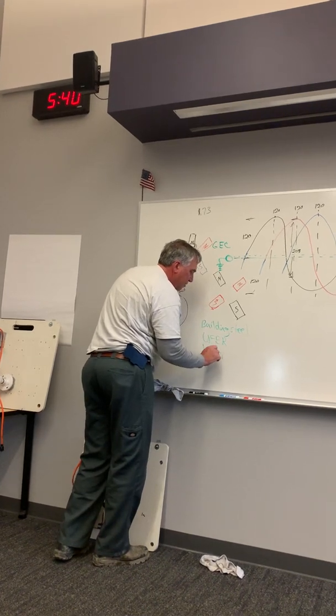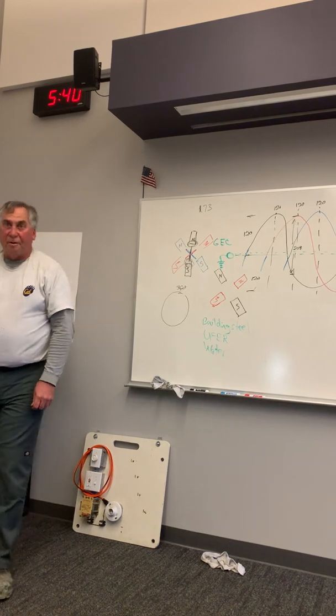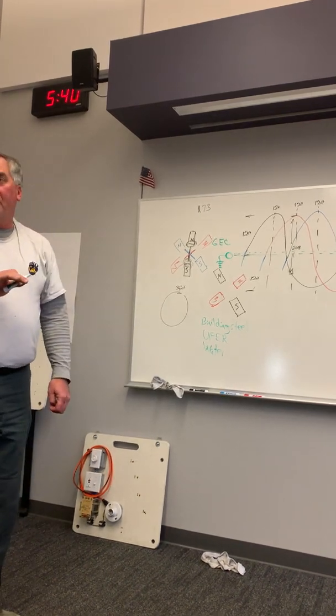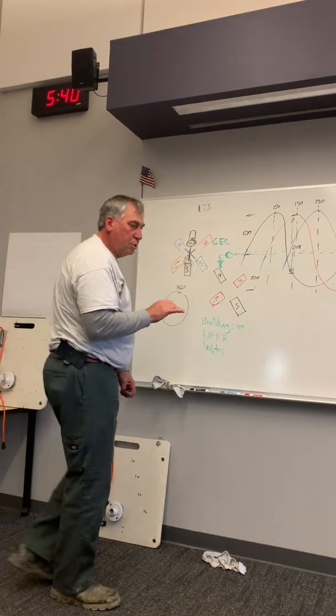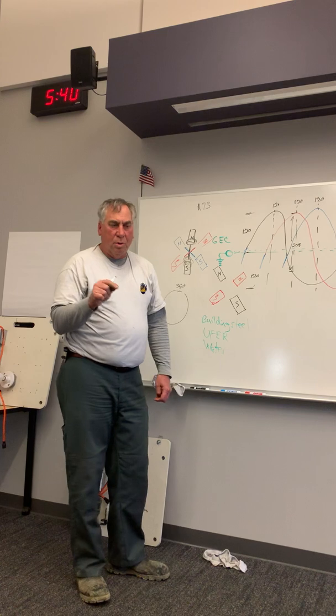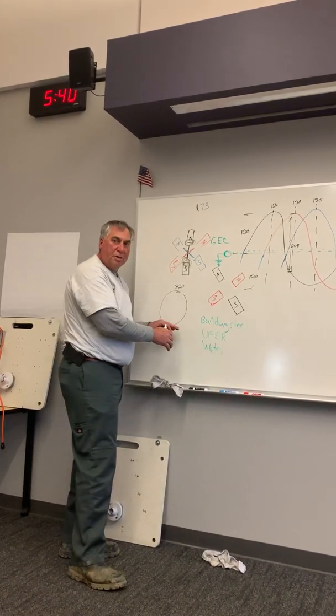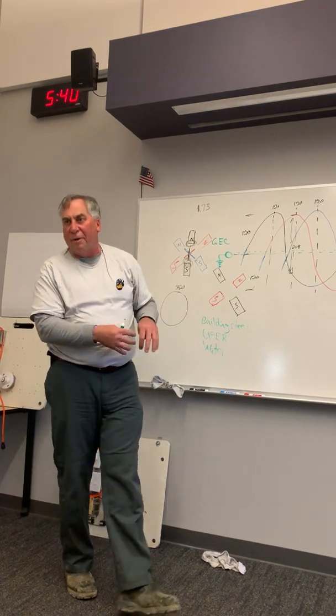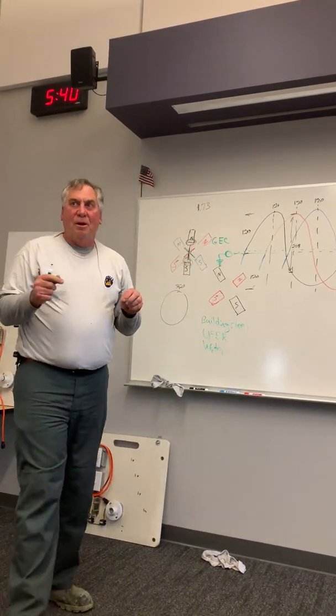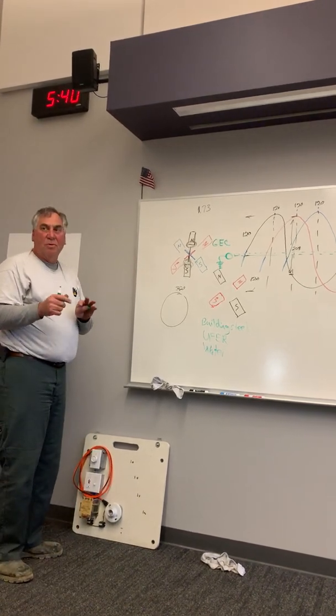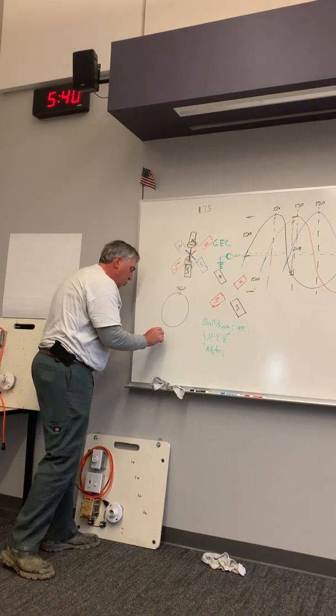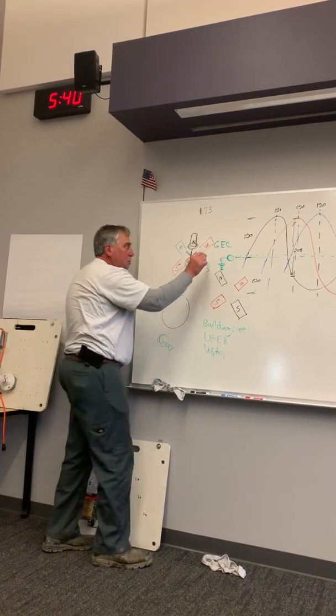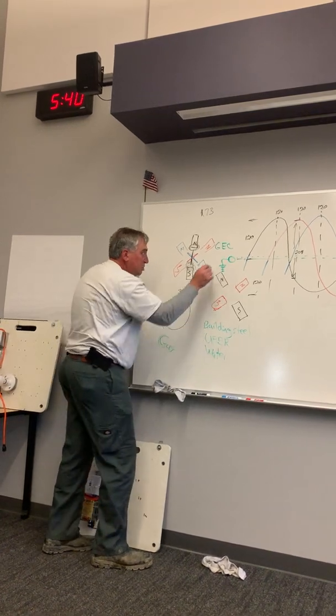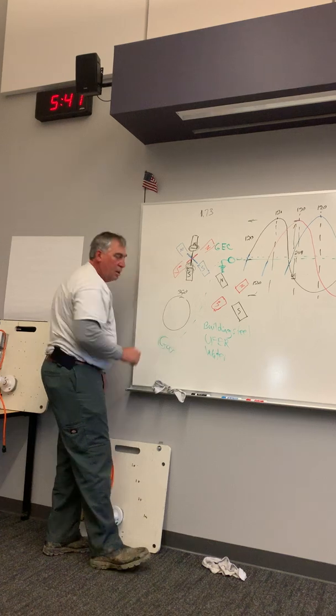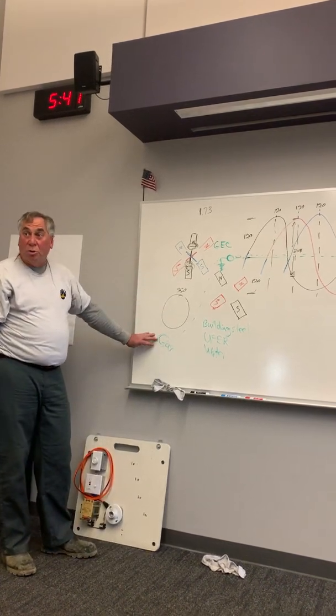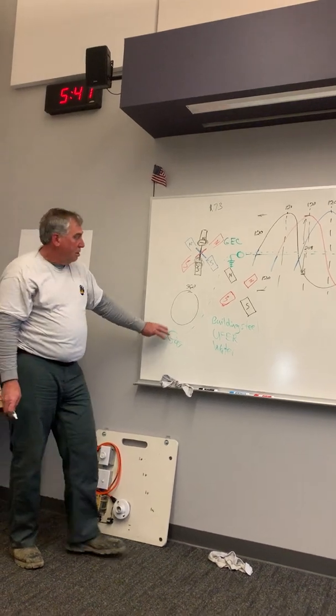I don't agree with using the gas pipe. We're not using the gas pipe as a bonding, I mean as a UFER ground. We don't want a gas pipe to bleed off any kind of fault current, and we don't want to induce fault current onto a gas pipe. That could be disastrous, right? But what they want you to do, when a gas pipe is involved, is bond it. So you're just bonding the gas pipe. It's not part of the GEC, but you always make sure you tie it in. Once you've established this ground, you can put a jumper in here and bond it, so that if there's ever any voltage induced on it by accident, it will go directly to ground and trip the overcurrent device.